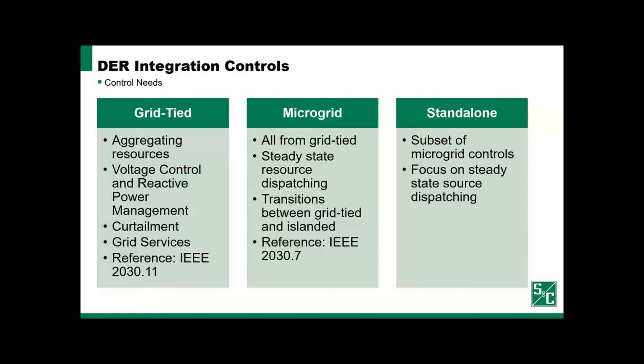In grid-tied systems, our controls will be responsible for aggregating resources to ensure we can effectively control the multitude of devices out on the system. Our controls will manage the voltage and reactive power, which, as you may know, voltage profiles change quite significantly with DER penetration, and it's more and more important with increasing DER penetrations to ensure that the voltage is controlled to maintain power quality to customers throughout the system. In some cases, curtailment may be needed to meet system needs, and a controller can manage those, deciding what devices should be curtailed and to what level.